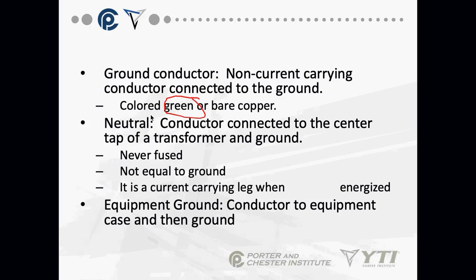Neutral is a conductor connected to the center tap of the transformer, and to ground - I'll explain that in a few minutes. It's never fused. It's not always equal to ground, but it should be close. It is a current carrying leg when energized, taking that current back to the bonding in the breaker panel. I won't explain this exactly like the electrical instructors do, they go much deeper into this as electricians, but basically it is your return to the breaker panel, because it completes the circuit.